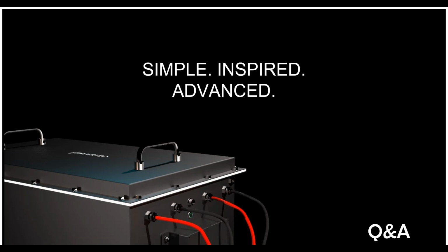The answer isn't as trivial as it sounds, because it's difficult to determine at what point in time how much load would be running. For example, when sizing a diesel generator, if your total sanctioned or connected load is 10 kilowatt, you'd assume that at any point you'd probably be running just 30% or 40% of the connected load. That's just a ballpark assumption for sizing. So if your total load is 3-4 kilowatt and you want a 4-hour backup, that means you need 12 units of usable backup.